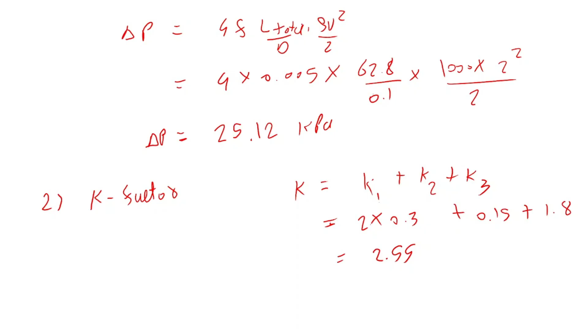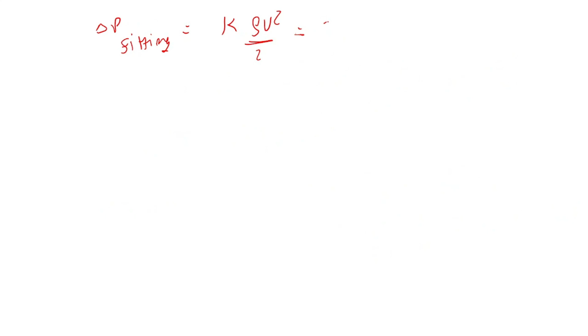Now the pressure drop due to the fitting, sorry, the pressure drop that will come in the pipe because of the fitting, how did we compute it? K rho v square by 2, right? And the K value came as 2.55, so you can substitute that and the velocity value and you will get somewhere around this value. Okay, now delta P in the pipe, again we have to use the Fanning Darcy-Weisbach equation, so 4 times F L by D rho v square by 2. Okay, but here L will be the actual pipe length, not the equivalent length, not the total length.